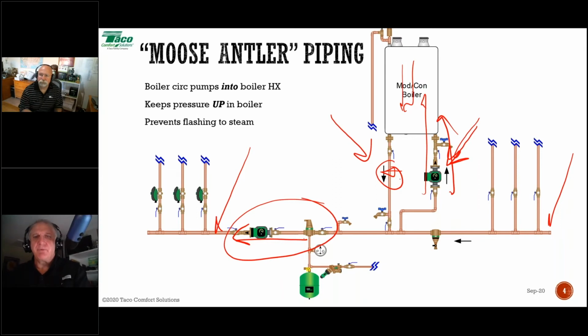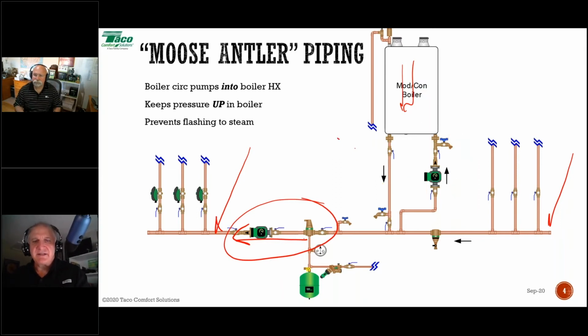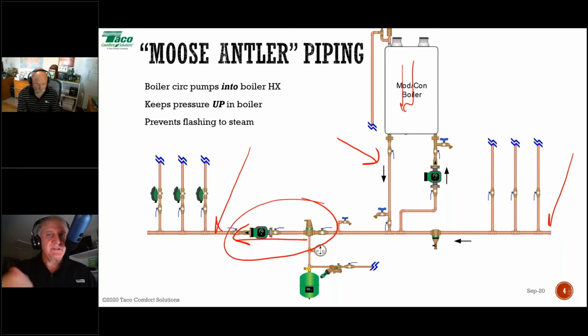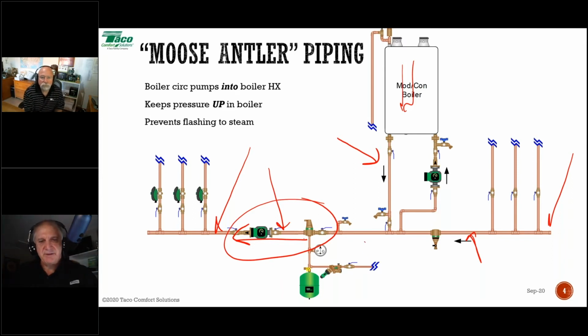Okay, the sizing of your boiler pipe. The sizing of this pipe right here is basically handled in the manual. They'll tell you what size pipe that should be, 3/4 inch, 1 inch. The manual, read the manual. The manual will tell you what that size pipe should be. Sizing of the distribution or the delivery header is going to be based on the BTU load of the system. All right, so say we have a 70,000 BTU house. So this pipe here has to deliver 70,000 BTUs.